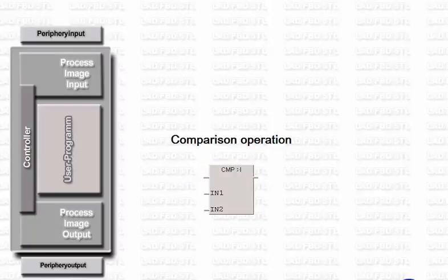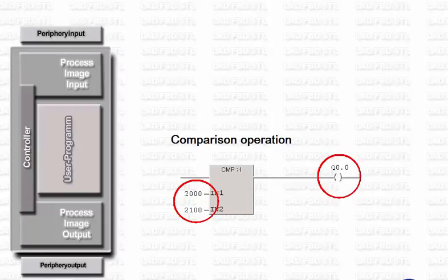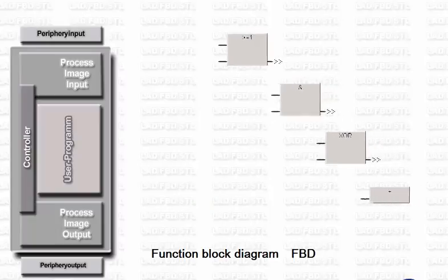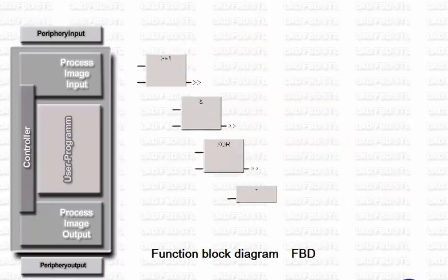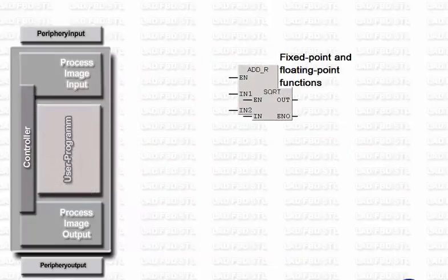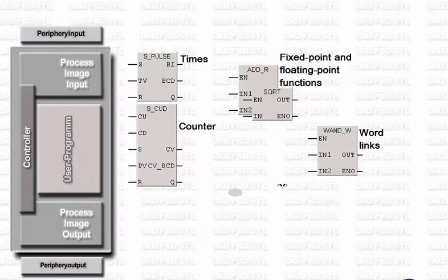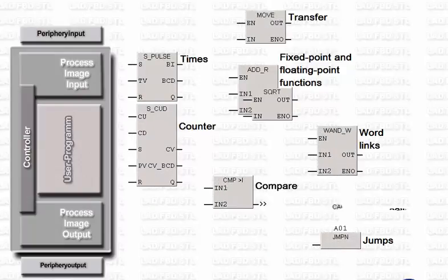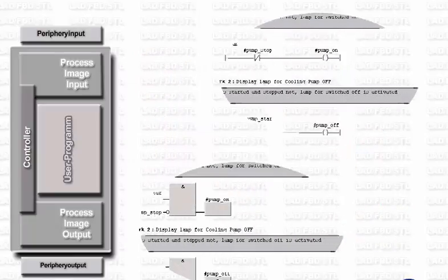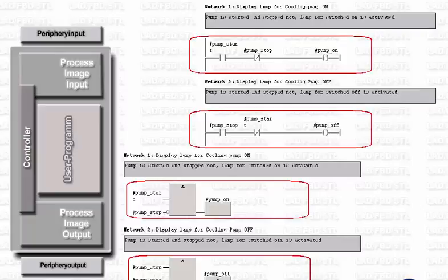Such a box can have several inputs to receive input values and provide the result to an output. In the programming language Function Block Diagram, or FBD, boxes are also used to implement binary combinations of signal states. As in LADDER, more complex functions are implemented by special program elements which are supplied with the required variables through the inputs. To structure the program, both languages use networks which terminate one combination sequence each, and thus represent the smallest structuring unit.